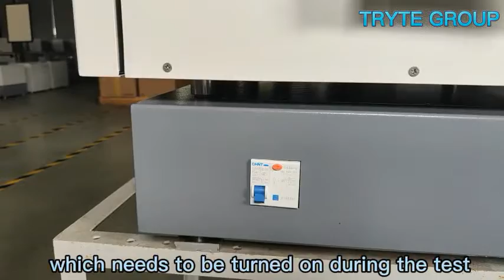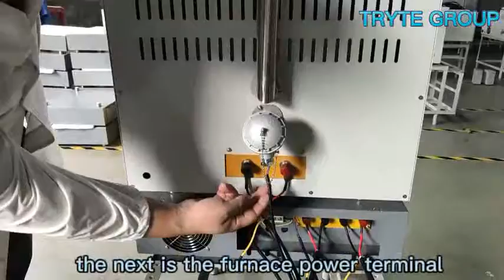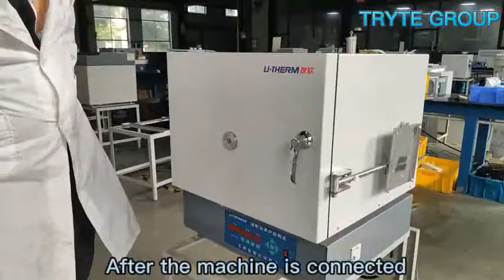Here is the back part of the muffle furnace. Starting from the top is the chimney, the middle is the thermocouple, the next is the furnace power terminal, and the bottom part is the power terminal of the control box, and you can connect it according to the instructions. After the machine is connected, turn on the power switch of the instrument, and turn on the heating power switch on the right. If there is no error displayed on the display, we can start to select the function program.